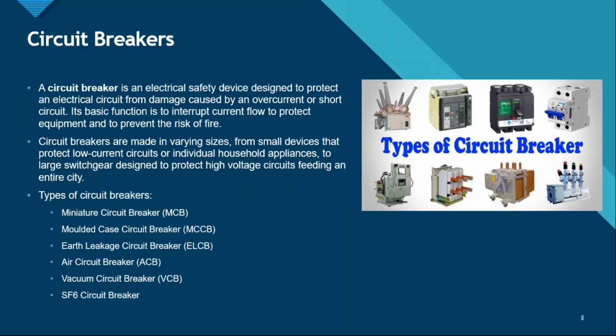Like we discussed, there can be different types of circuit breakers based on the current rating of the system. Here in the photo that you see, the first, the top left of the circuit breakers mentioned, is the SF6 circuit breaker, usually on a power transformer that is outside, all right, in your substation. Next to it is the air circuit breaker, usually located on your electrical panels in the electrical room. Next to it is the MCCB, also known as molded case circuit breaker, right? Next to it is the MCB, mainly on the electrical panels, right?